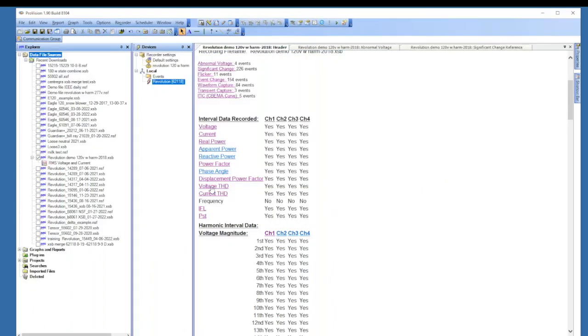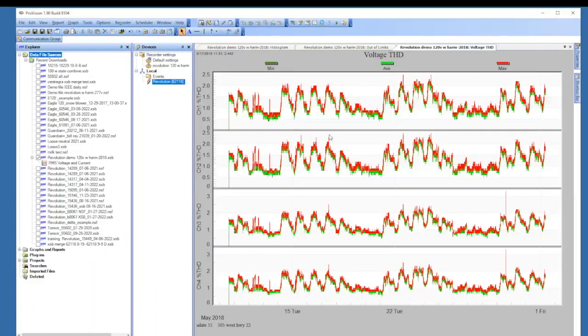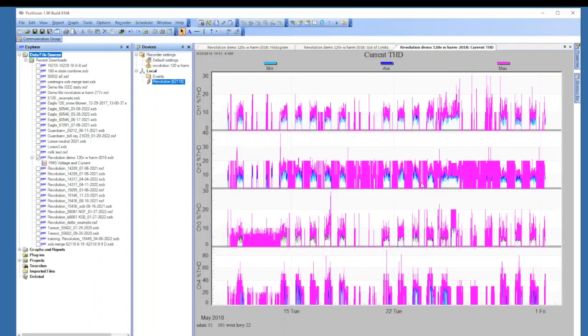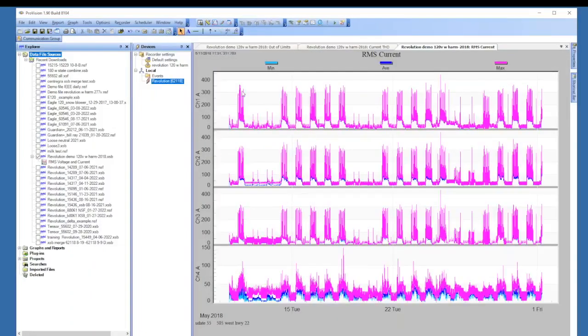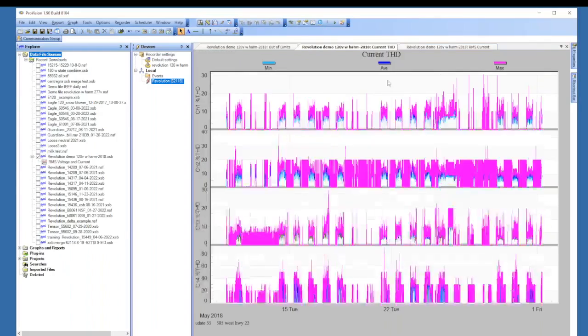So voltage THD, again, 5% is what you're looking for. Less than 5%, I should say. So you can see here we're not even getting up to 2.5%. So our overall total harmonic distortion for voltage is good. Current THD, ITHD, you really need to go further in. You need to find out how much current we are actually running. So we're hitting upwards of 300, 330, 340. So this is a percentage of that.